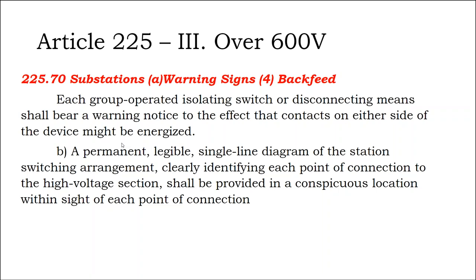So as a solar guy, if you just stick to section 690, the solar section, then the local jurisdiction hits you up with all these labeling requirements that aren't in 690. There are bases for requiring disconnect placard directories and single line diagram placard directories in other parts of the National Electric Code.